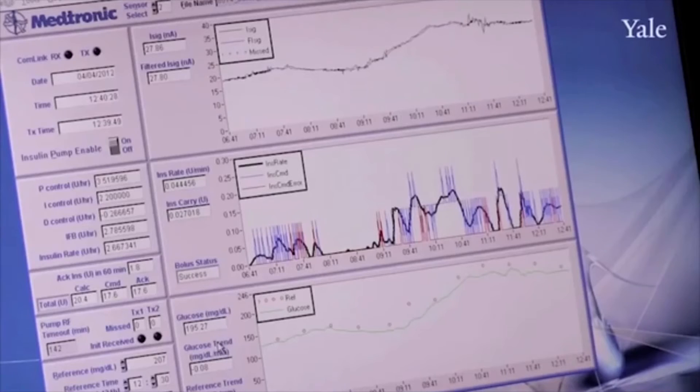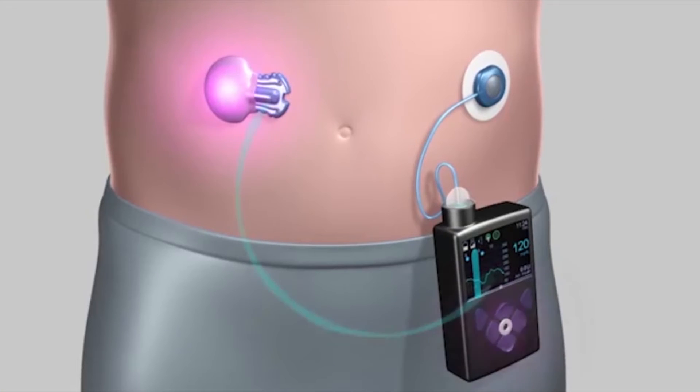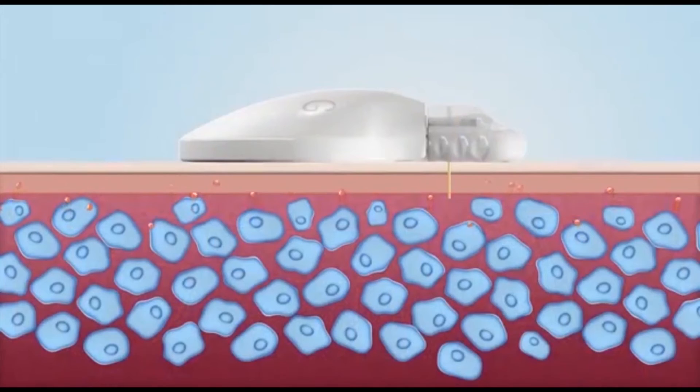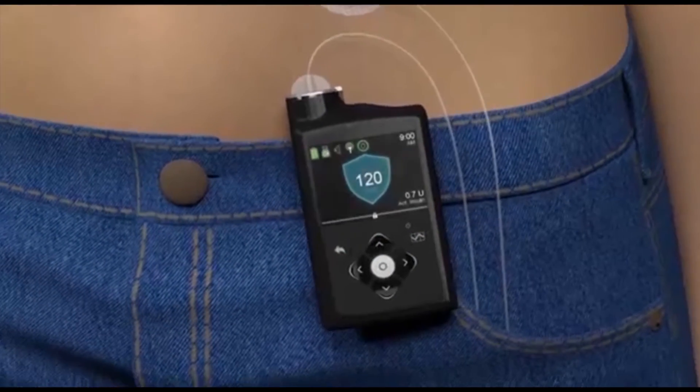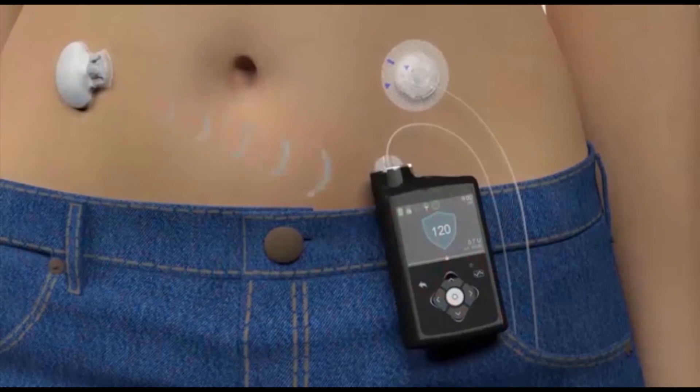Continuous glucose monitor or CGM provides a steady stream of information that reflects the patient's blood glucose levels. A sensor placed under the patient's skin subcutaneously measures the glucose in the fluid around the cells which is associated with the blood glucose levels. A small Bluetooth transmitter sends information to a receiver. A CGM continuously displays and estimates the blood glucose levels, their direction and rate of change of these estimates.